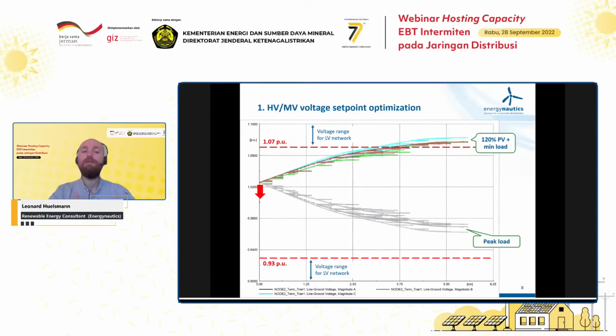However, if we have a lot of PV generation in the network, then during times of lots of solar PV output and limited load, we will see a voltage rise. Depending on the regulation, you may have too much voltage rise, so that your voltage is outside of regulated boundaries. So this is a problem. You have the regulation that guides this, but also all the devices in your house expect a certain voltage level, so it should be kept in a certain range.